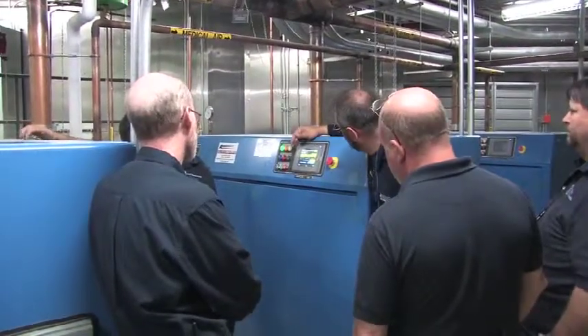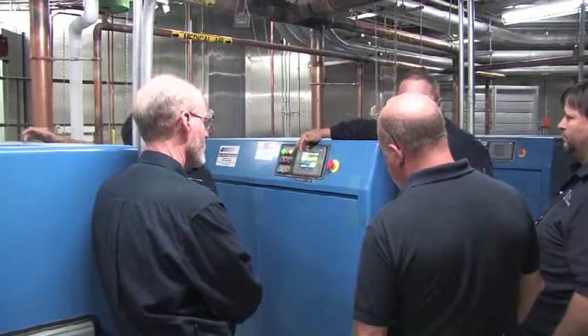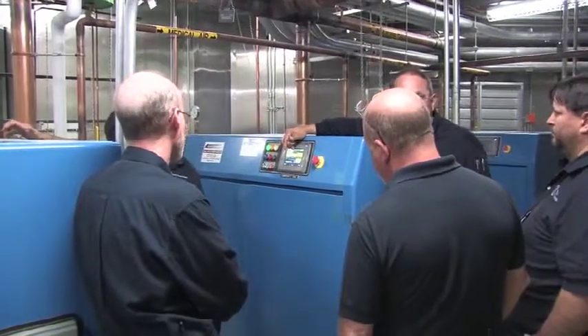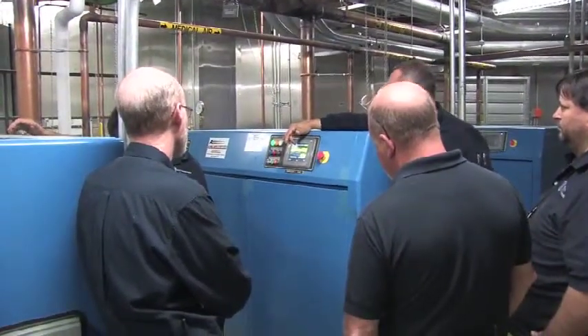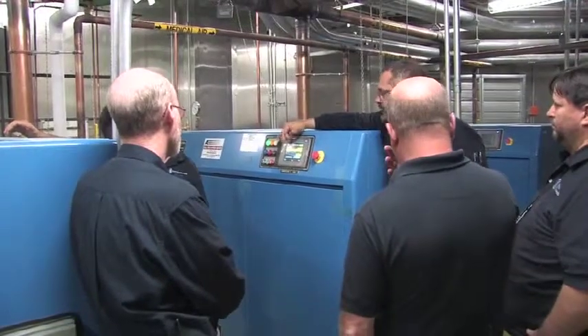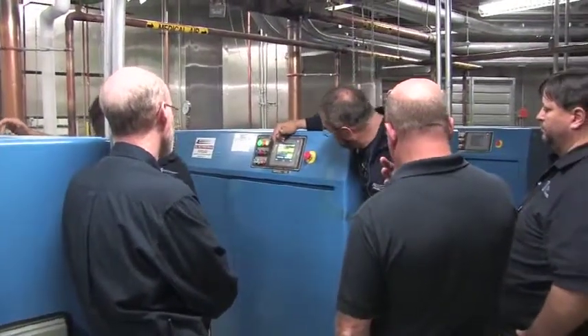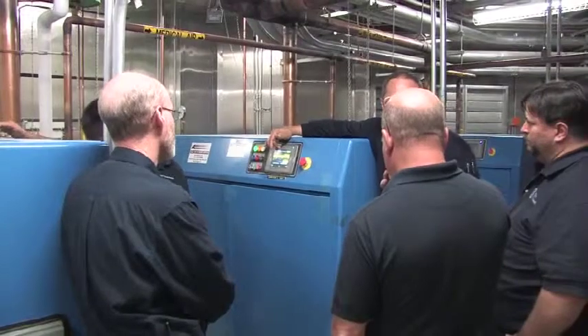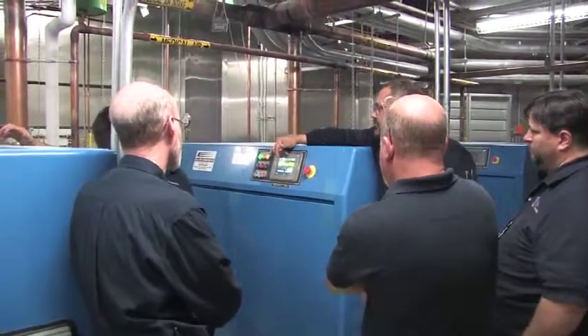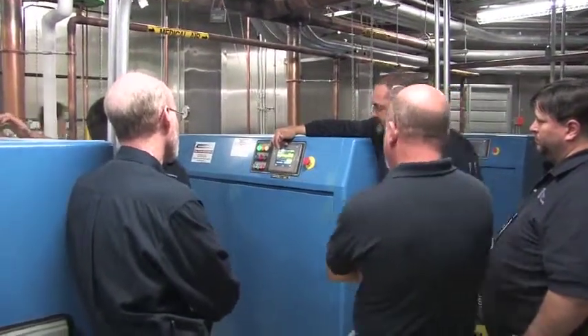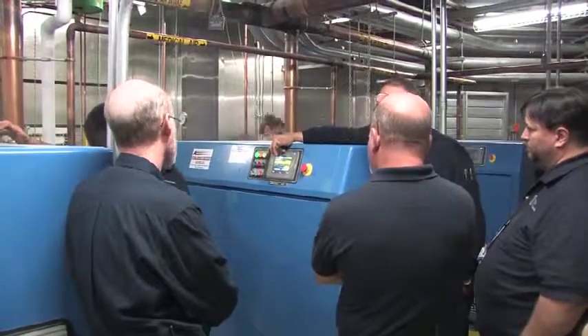So you get your intake, the other critical one, the interstage pressure, which as you all know, I'm sure, is one of the two things you're supposed to check when doing daily rounds or whatever. The recording sheet for these machines says to take this pressure when it's at 30 inches, when it's in vacuum while it's running.